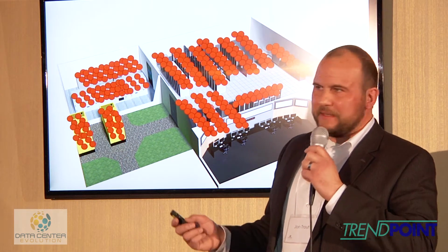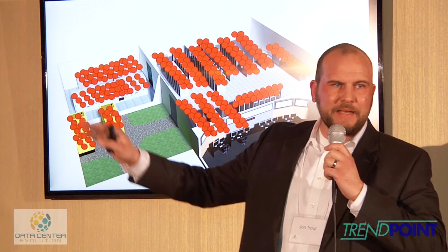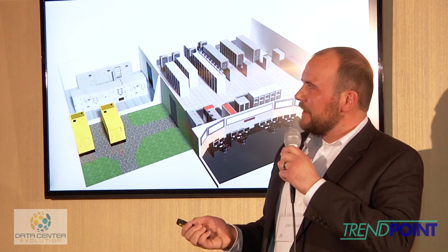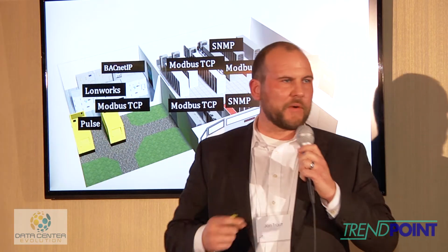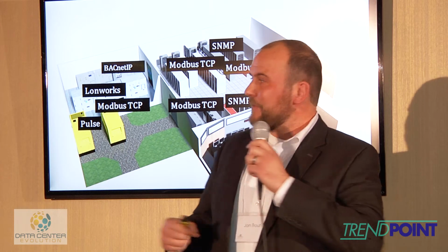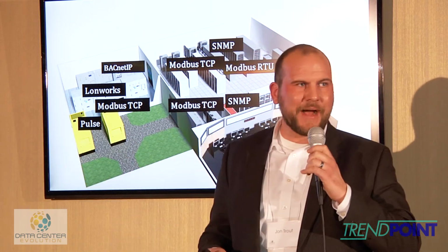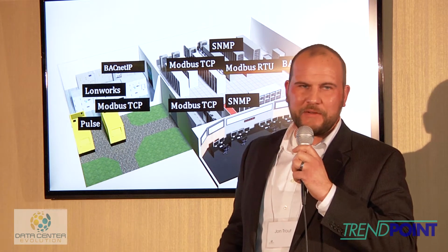And so the data points in this data center would look something like this. And it's not just the sheer number of data points. What happens is you're dealt with something like this, and you see different protocols, you see different manufacturers' devices, different SNMP MIBs, different Modbus maps. Some of them are even pulse technology on some of the older generators, so then you're buying converter boxes to get that data into the software. And so this is really where the issue comes in.